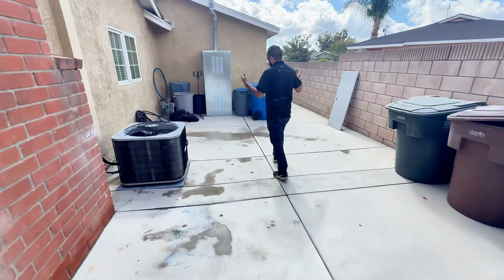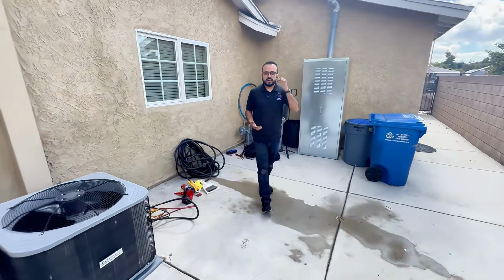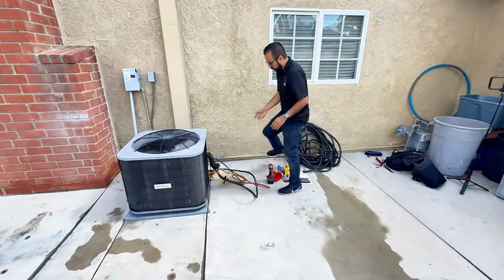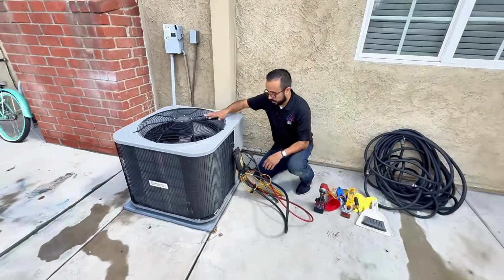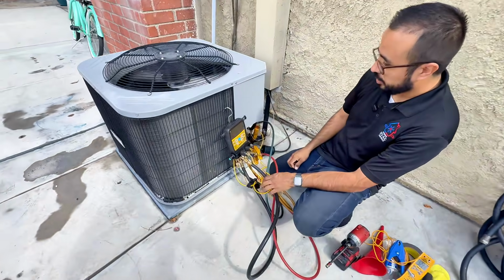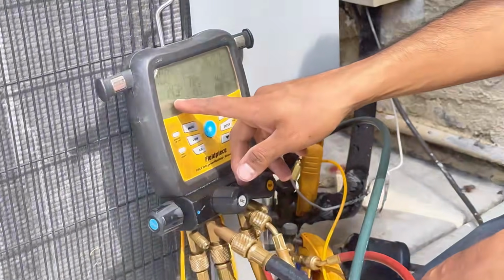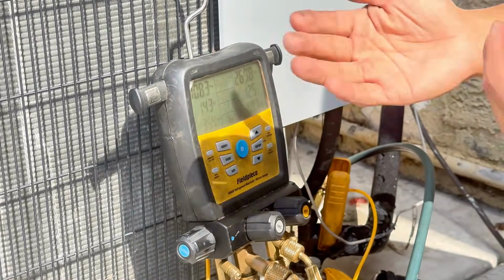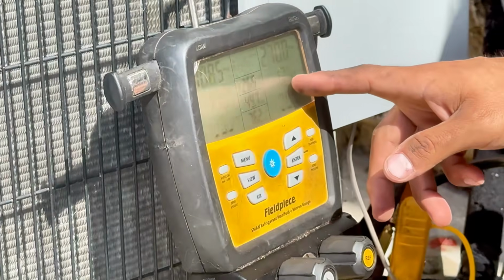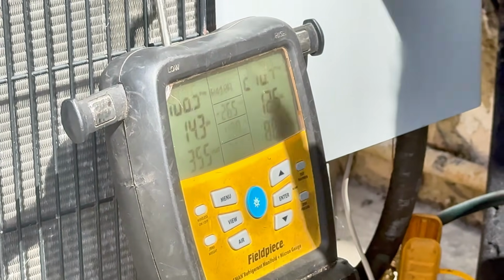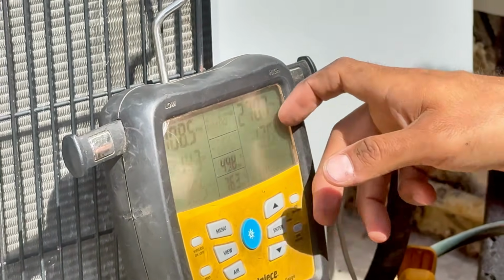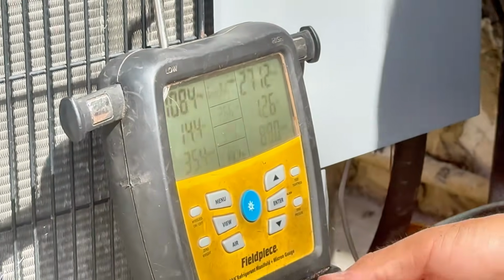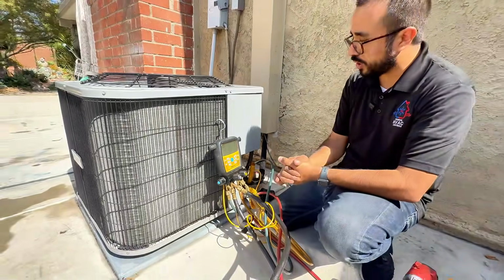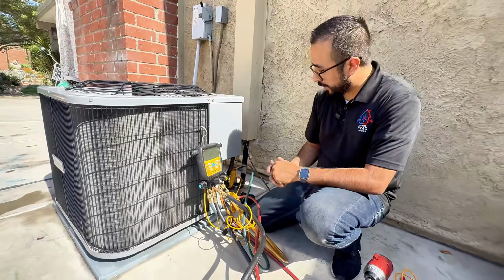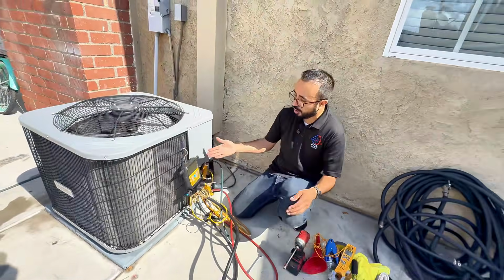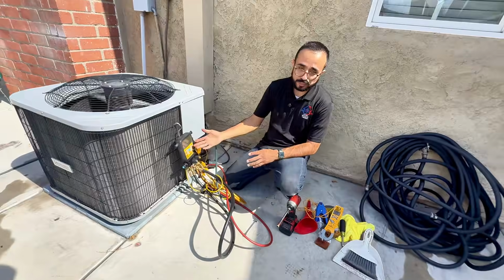All right, friends. So I do like what I saw inside. A good delta T. We come back to just see our numbers here. My superheat is 14. The TXV is adjusting. It's working great. My subcool is at 12. So yes, it's a TXV system, so we're looking at subcool more. We have about a 12-degree subcool. So our system's working great. I'm very happy with it. Now, you might not be able to start off with S-mans. You know, these are pretty pricey.